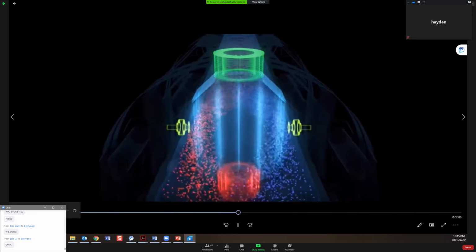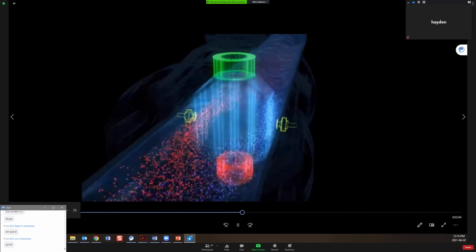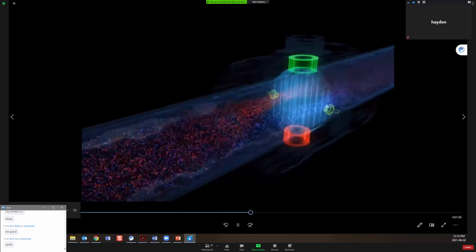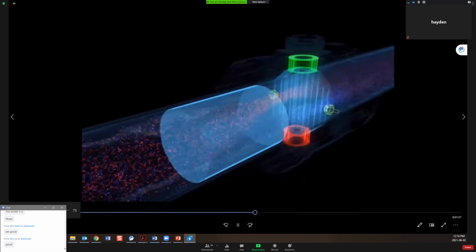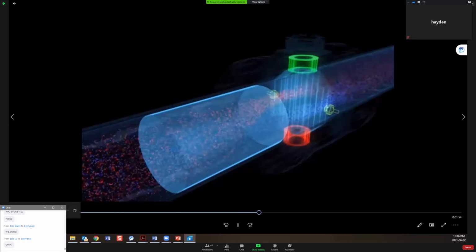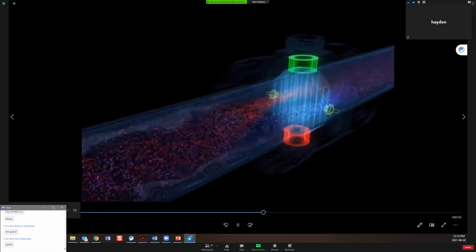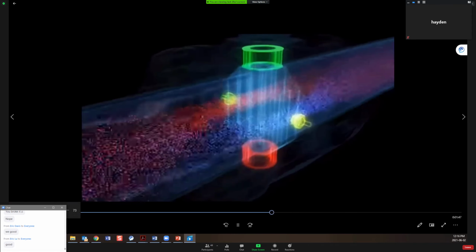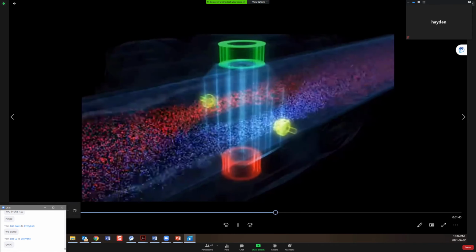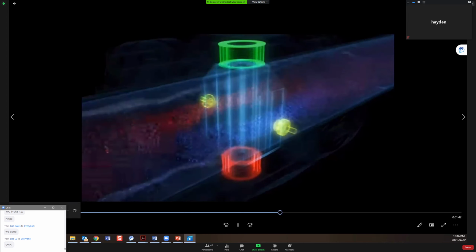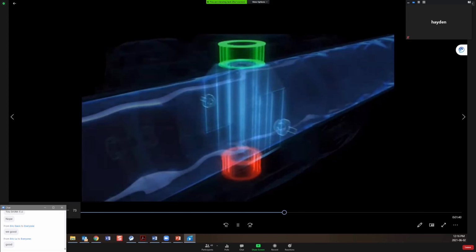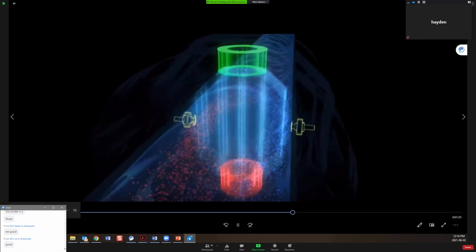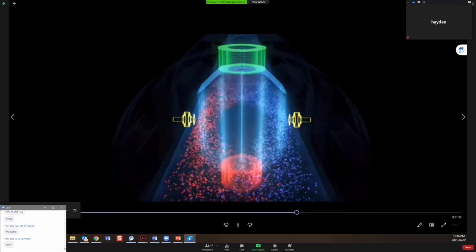This voltage is directly proportional to the flow velocity in the pipeline. Together with the known tube cross-section, the flow volume can then be calculated. The greater the flow velocity, and thus the separation of the charged particles, the greater the electrical voltage between the electrodes. The electrodes also detect what is called interference voltage, which has to be separated from the actual measuring signal.